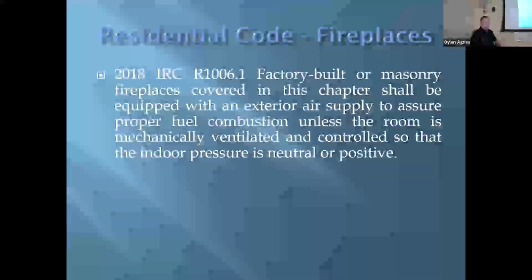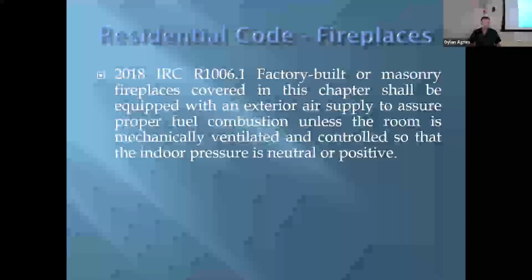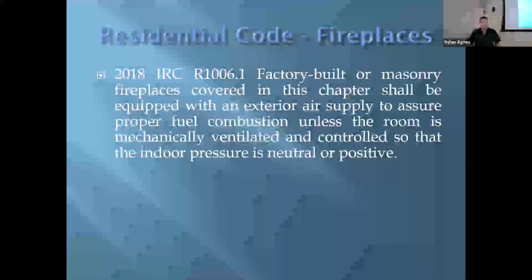So what started this, we had, and we still have problems. Probably the most recent one was about 4 months ago. And what is most common is the fireplaces are backdrafting. And these are typically open hearth fireplaces with doors. And they won't light. They'll either backdraft into the room, they can't get them going, or they'll start backdrafting while they're trying to light the fire and smoke comes into the room.